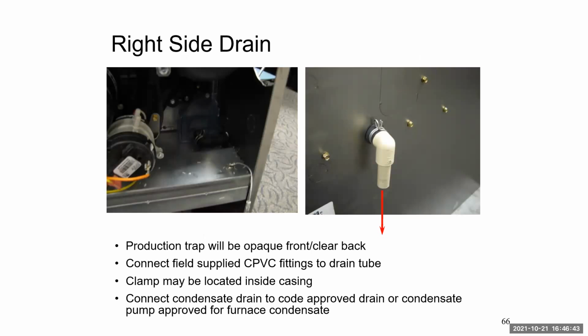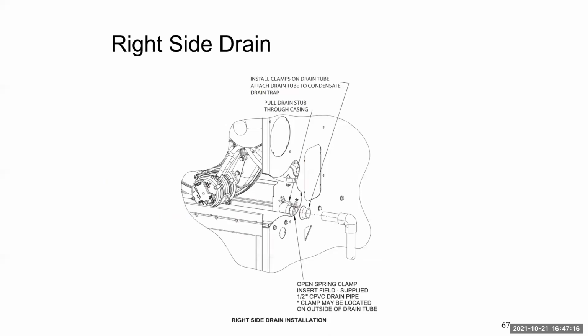When you're putting your 90 on the outside, don't glue that in. It comes with a clamp for a reason. If you glue that in, anytime you have a problem, you're cutting that all apart and you're replacing it all. Clamp it in. The exit of your 90 can be glued in, but where your rubber hose meets your 90, that's in your loose parts bag, use that clamp to hold it in place. Do not glue it in. Kind of just showing you how to put it in and where to clamp it.